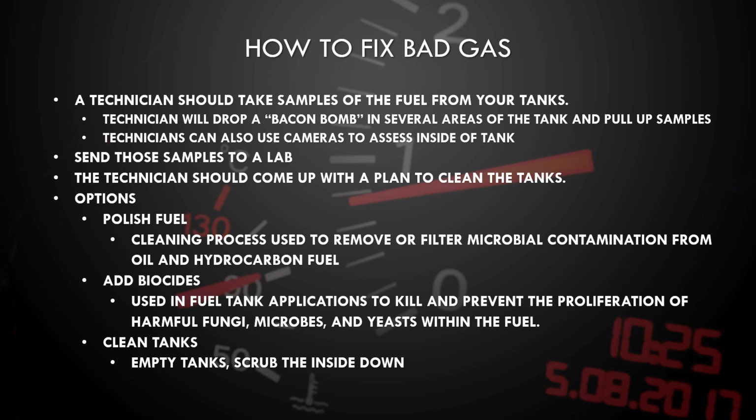Adding biocides, in case there are microbes in there, sometimes they'll add biocides to kill off those microbes. But even if they do that, sometimes the microbes will then settle in the bottom of the tank and create a debris buildup called gunk or sludge or debris. And then you can clean the tanks. Actually physically have some kind of system set in place that scrubs the insides of the tanks.